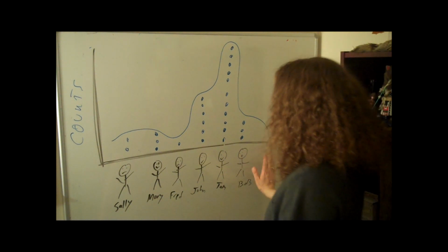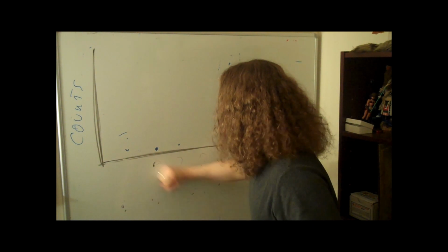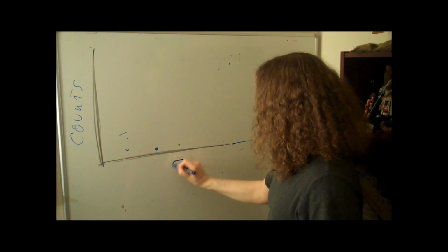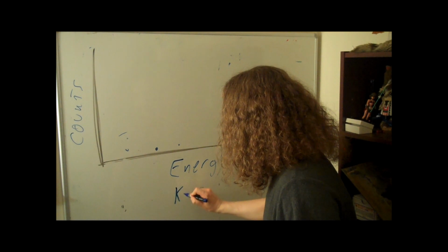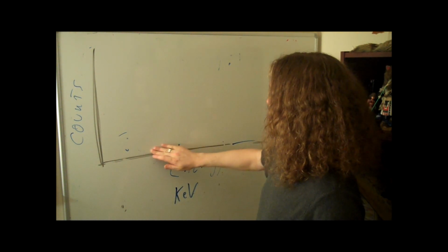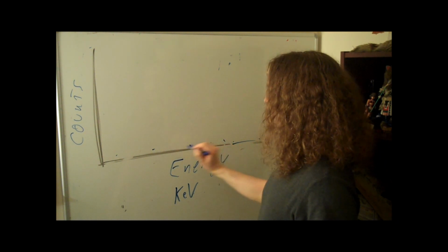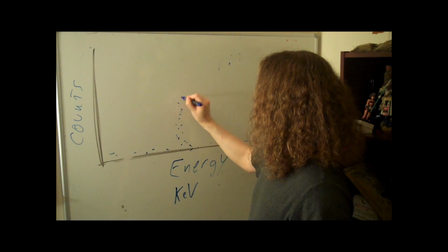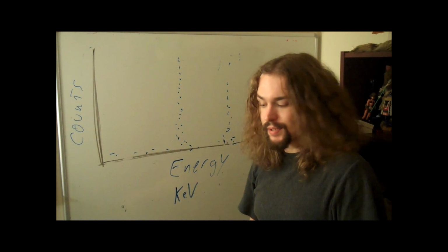That's the idea. So when you look at a scintillation graph, what you're seeing, and I'll show you this in just a couple of minutes, is energy expressed in kiloelectron volts. Those are thousands of electron volts. That's just the unit that we use. Versus counts. So, as the little gammas start to appear, and they start to enter at the bottom, there are little channels down here, certain areas are going to get more than others, and they're going to produce peaks that we'll be able to detect. Simple as that.